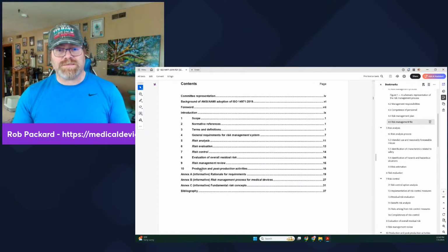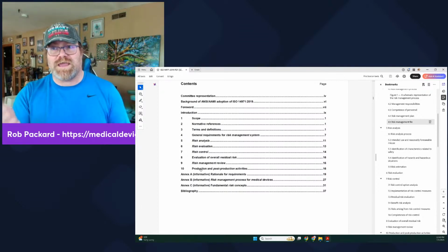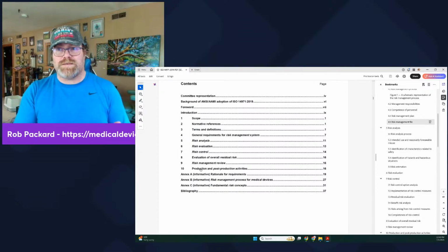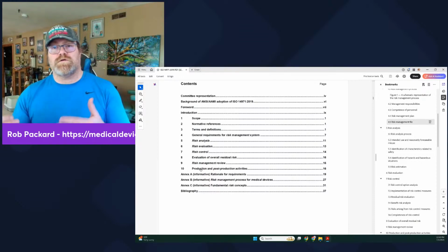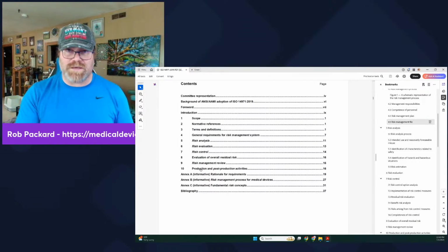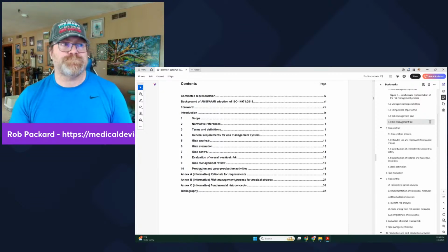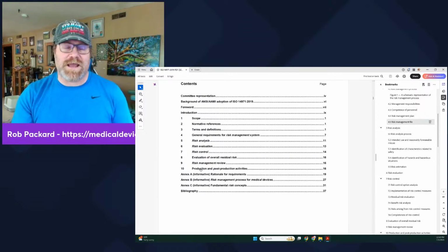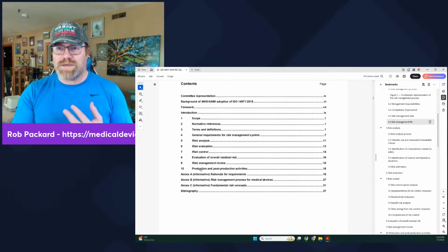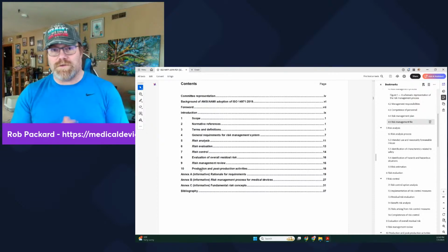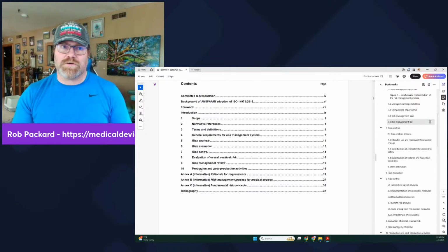But it is not possible to take a reduction in risk for detectability when we're talking about design because it's already too late. It's in the person's hand. They're not an automated piece of equipment that's going to check for defects. They're just going to use it. So you don't take deductions for design for detectability. You only take deductions for detectability in process when you're making the product. So we have typically a design FMEA where we have 2 key things we're looking at, the severity and the probability of occurrence.